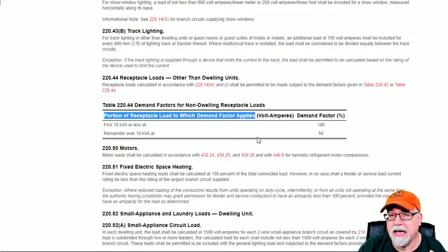That is all you're going to highlight because that draws your attention to it, okay? Now, since we're here, how are we doing this? Well, we already have our connected load. It's 36,000 VA for these receptacles at 180 VA per strap for 200 of them.